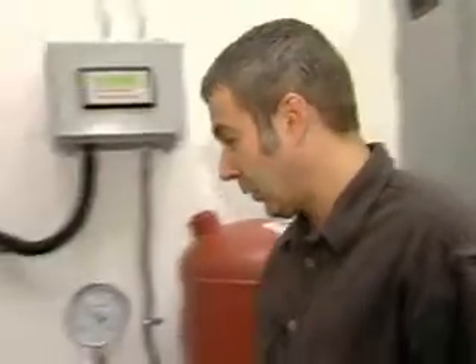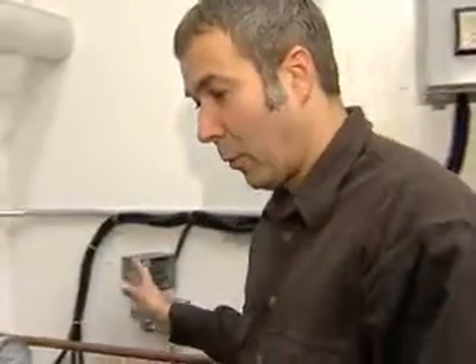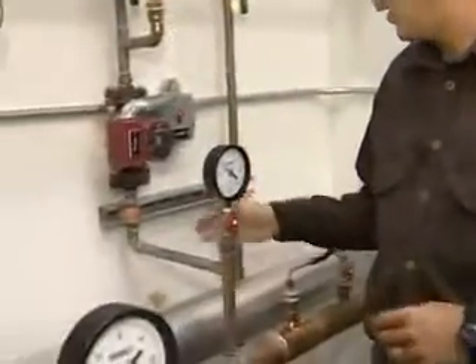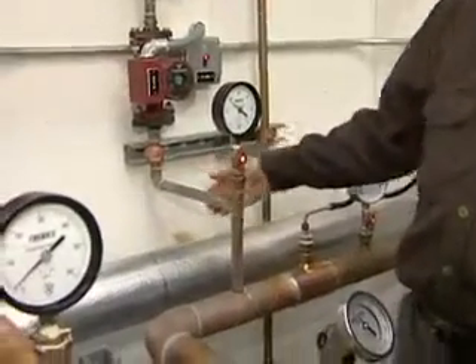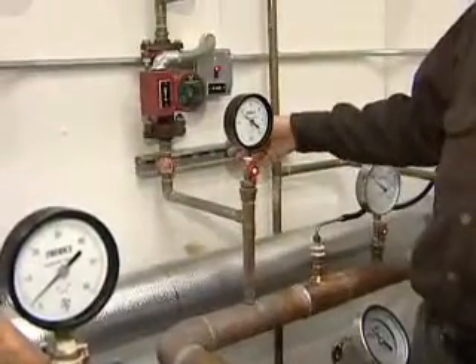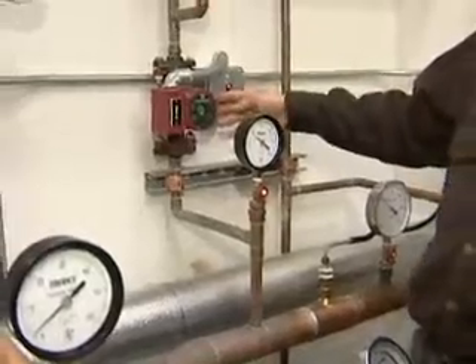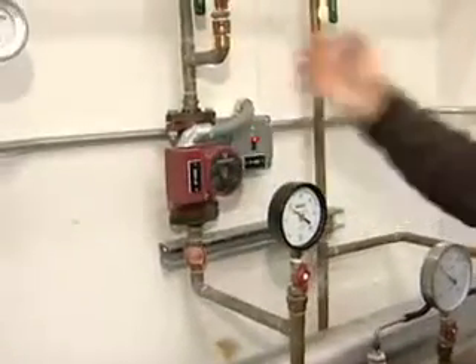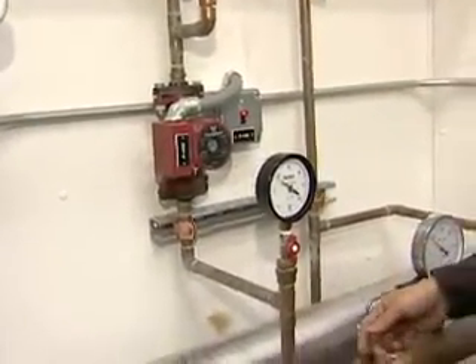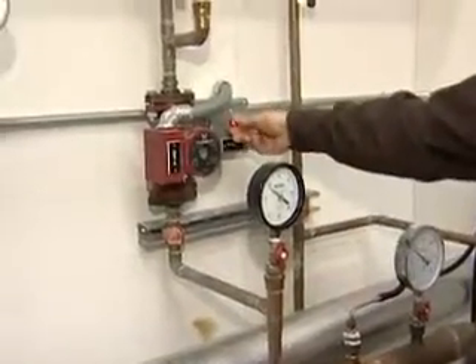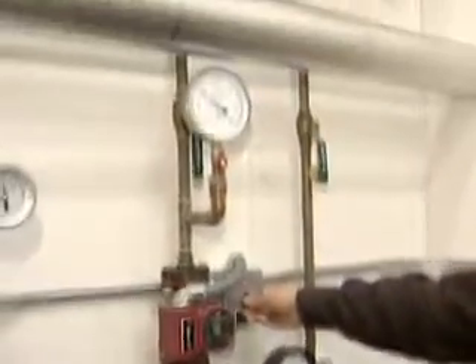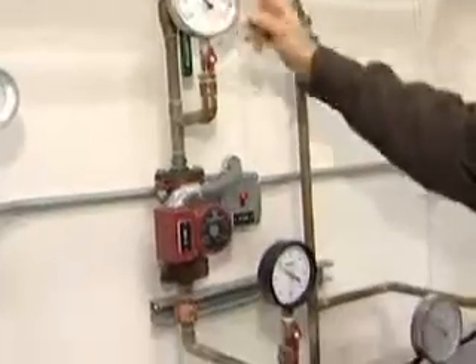Okay, now in this system, the waste heat goes to a remote building, which we'll look at in a little bit. And we also come off the waste heat system and provide heat to the other rooms in the power plant, which we'll go through. So we have this small pump here, and this one serves the unit heaters in the control room and the storage room. And again, we can see that this pump is operating by turning the switch on and off and seeing the pressure gauge vary.